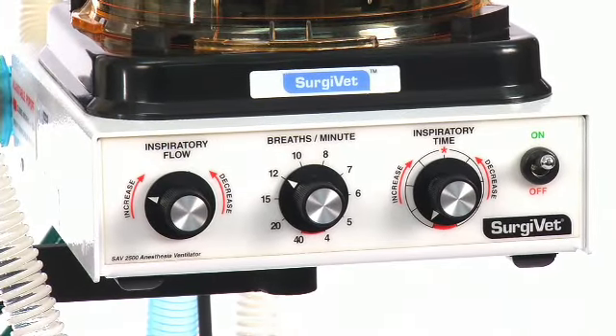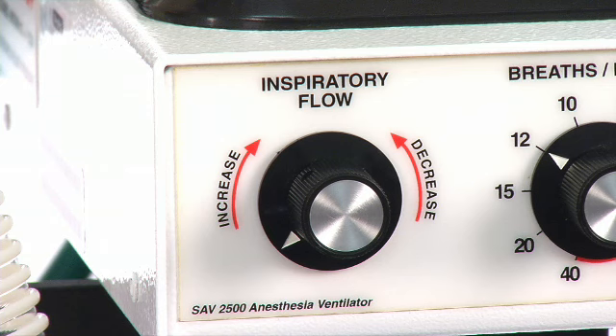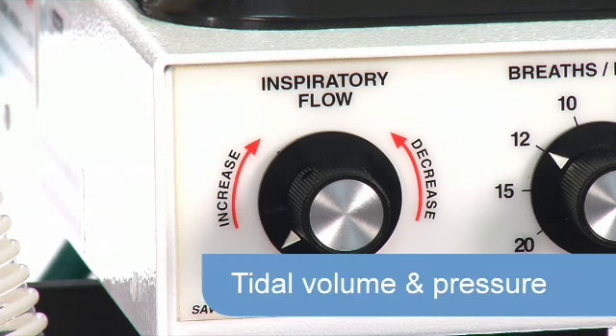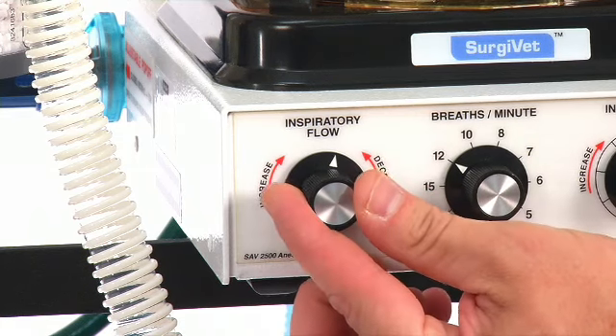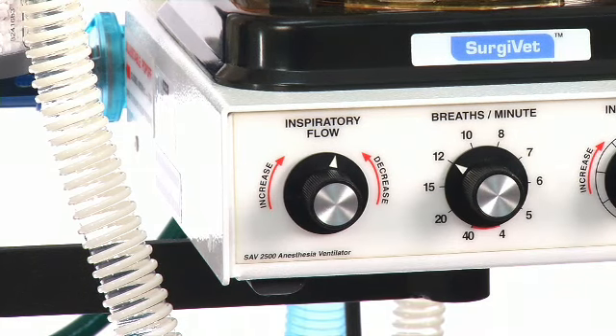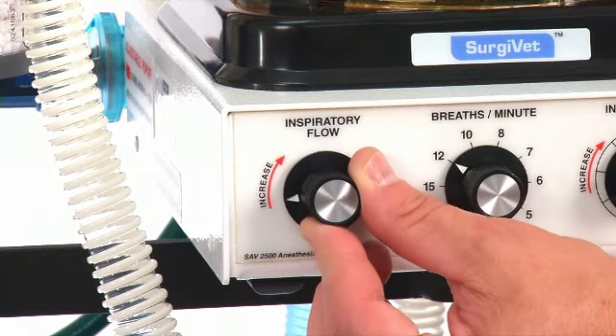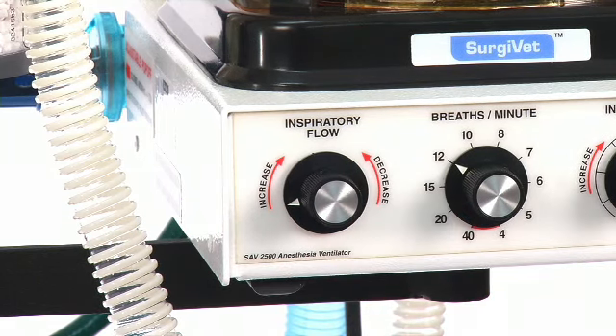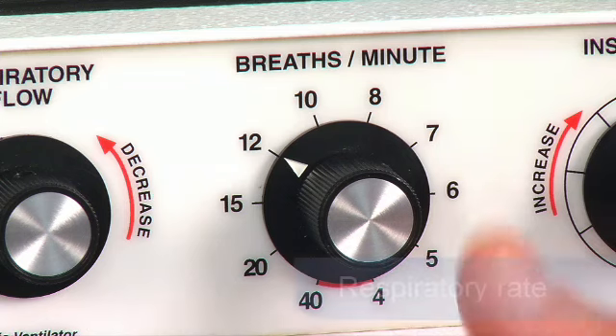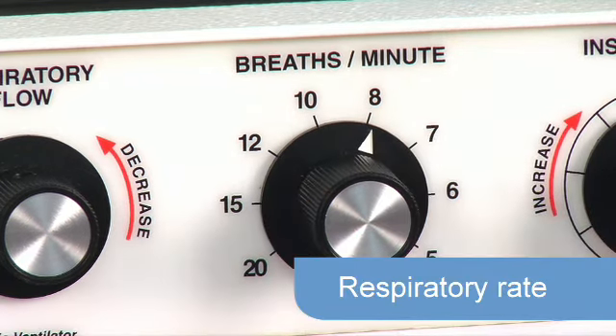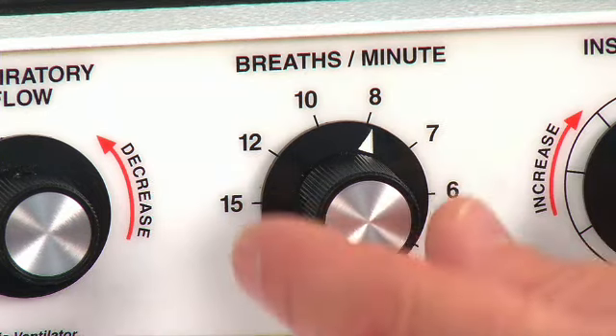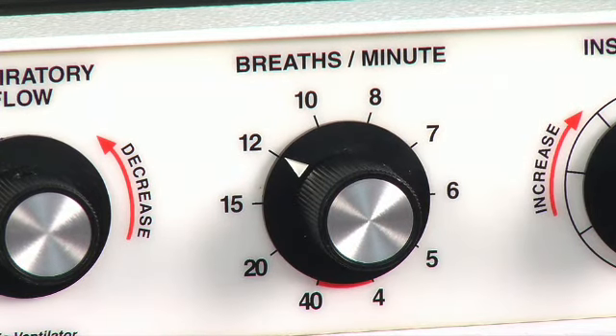The SAV2500 ventilator has 3 control knobs. The knob on the left controls the inspiratory flow, which affects tidal volume and pressure. Turning this knob clockwise increases the volume and pressure of the breath delivered. Turning it counterclockwise decreases the volume and pressure of each breath. The center knob manages the respiratory rate. Please note this is variable based on the other control settings.